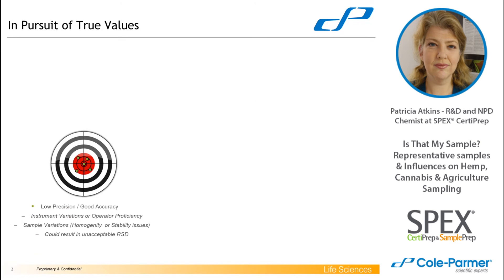If you're thinking about good accuracy, that's when your numbers are near your target. So if you are aiming for five parts per million and you're getting four, five, six — you're getting them in a good range, sort of hitting that target, but they're not on top of each other. So you're getting really good accuracy but kind of low precision. This can be due to instrument variations, like an auto-sampler or operator proficiency — maybe the operator is hand-injecting slightly different amounts each time. It can be sample variations — maybe your sample's not homogeneous or there are stability issues — leading to an unacceptable RSD, or relative standard deviation.